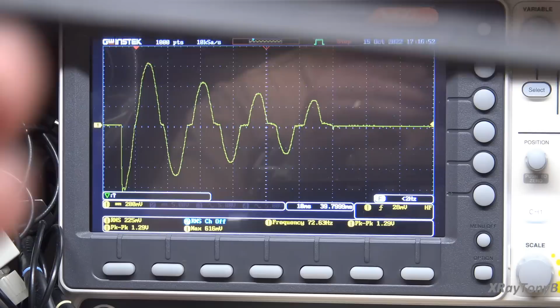So if you look, our very first pulse here, when we first turned the amplifier on, you can see there's a negative going and a positive going, and I'm set to 20 volts per division, because this is a times-100 probe, and lots of math, huh? Just take my word for it: each square represents 20 volts. So we have 20, 40, 60, a little over 60 volts. And if you take 60 volts divided by 2.7 ohms, because I measured this at room temperature at 2.7, you have about 22 amps of inrush current. So we're limiting the inrush current to this amplifier to 22 amps.